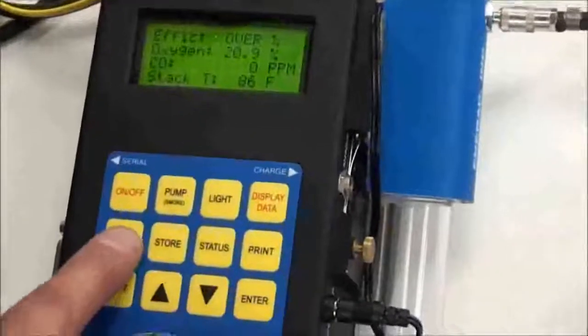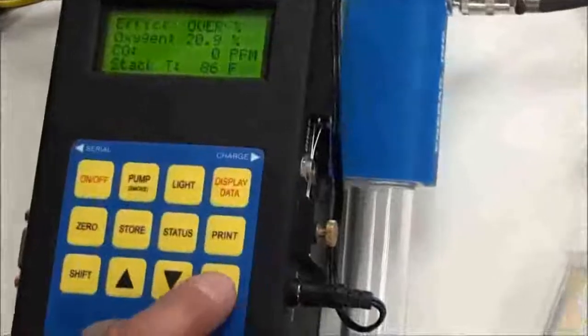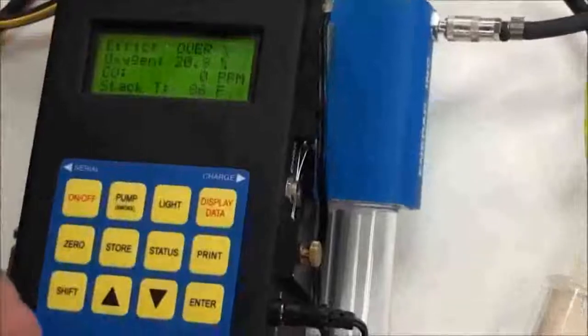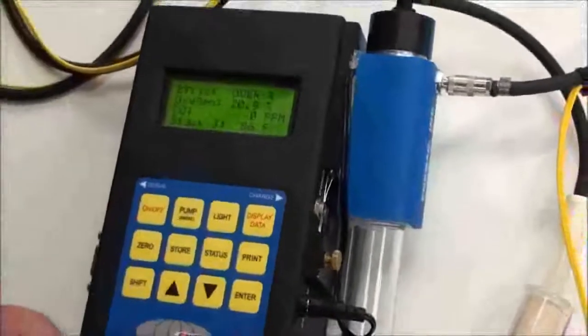You run the auto zero by pressing the 0 and then enter, and you will see a countdown. It will count down from either 120 seconds or 180 seconds down to 0. At the end, it will zero all the sensors. Oxygen will read 20.8, 20.9. All the other sensors should read 0. The stack temperature should read what the ambient temperature is. So when you're finished, your stack temperature reading gives you gross stack temp, not net stack temp. It includes the ambient temperature in the reading, so keep that in mind.